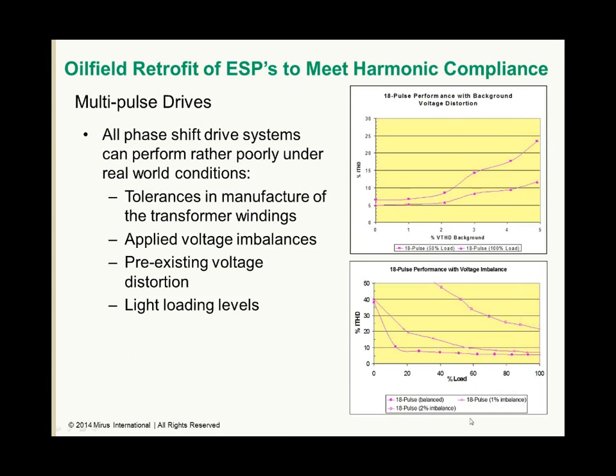Even worse is what happens when there's imbalance in the power system. This shows that same 18 pulse transformer with perfectly balanced voltages, and you can see the reduction in current distortion is very good. Performance is excellent. But as soon as we introduce 1% imbalance, you can see the THD increases. 2% imbalance pretty well leaves the chart, and the performance is no better than a 6-pulse VFD without harmonic treatment.